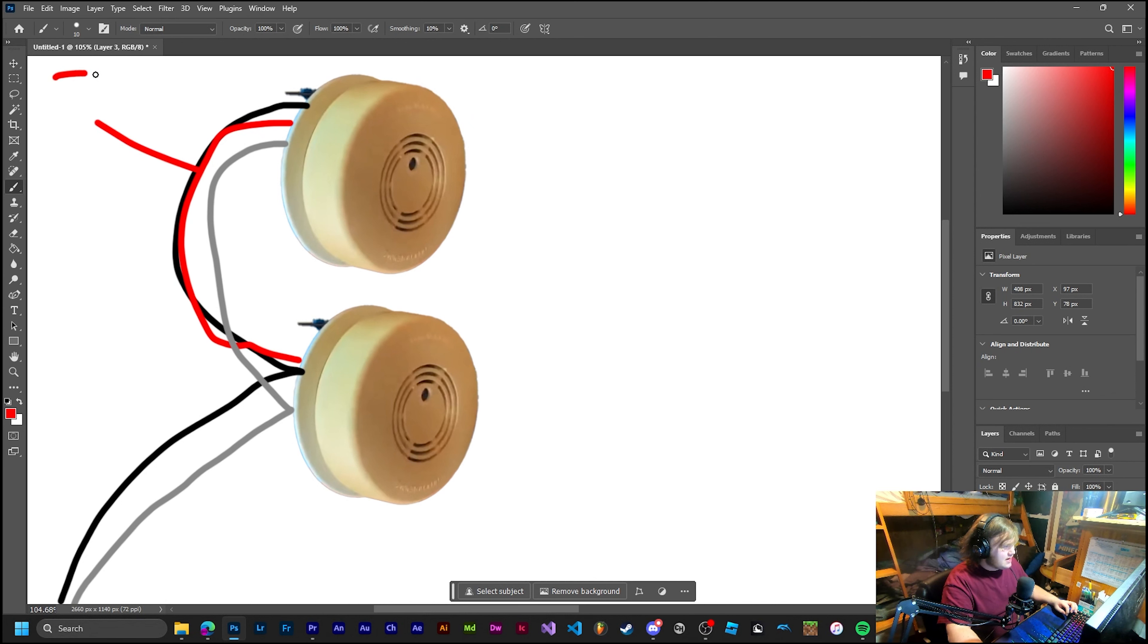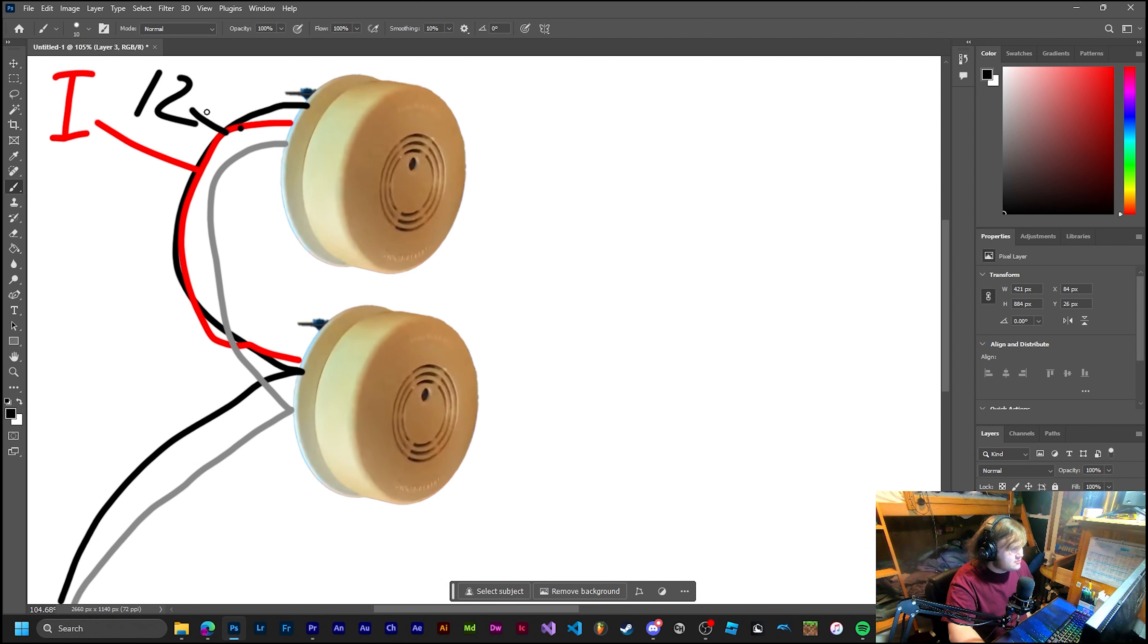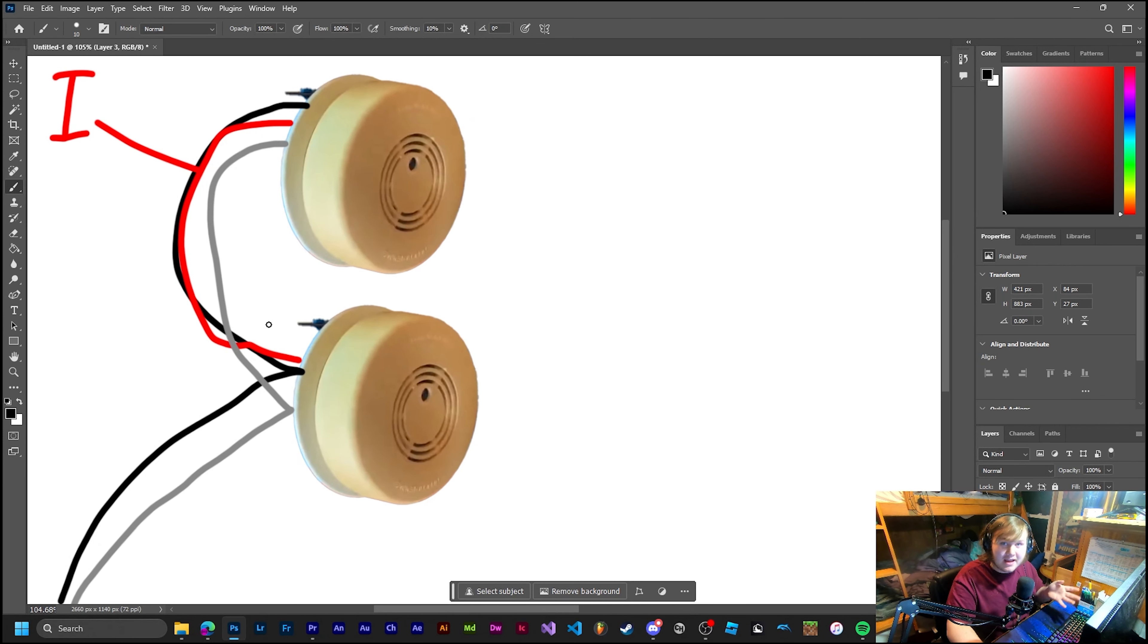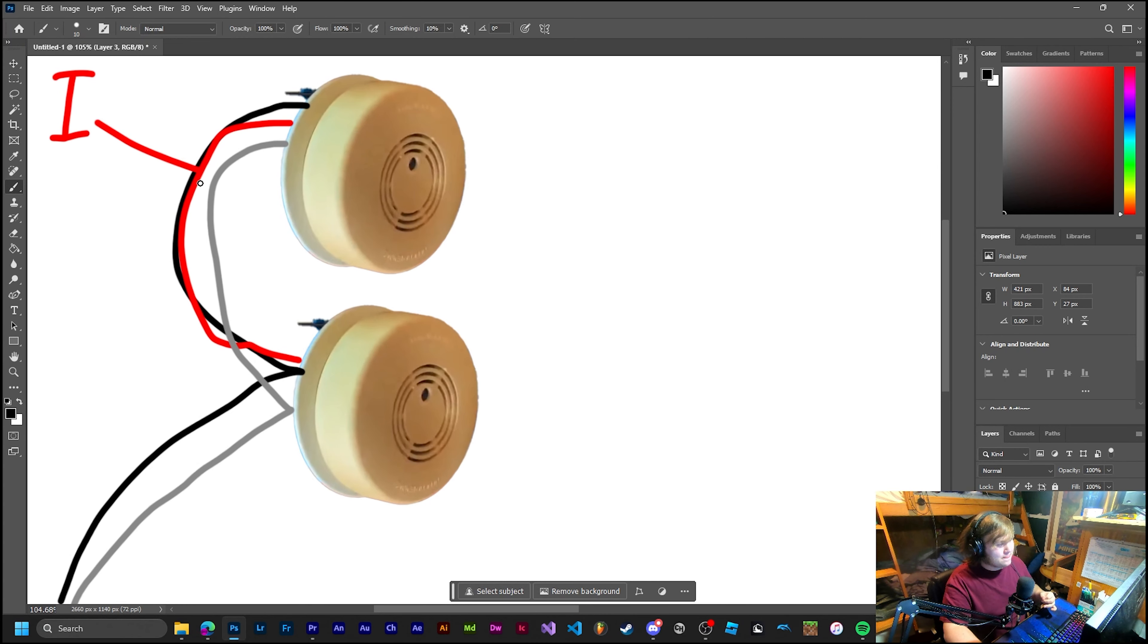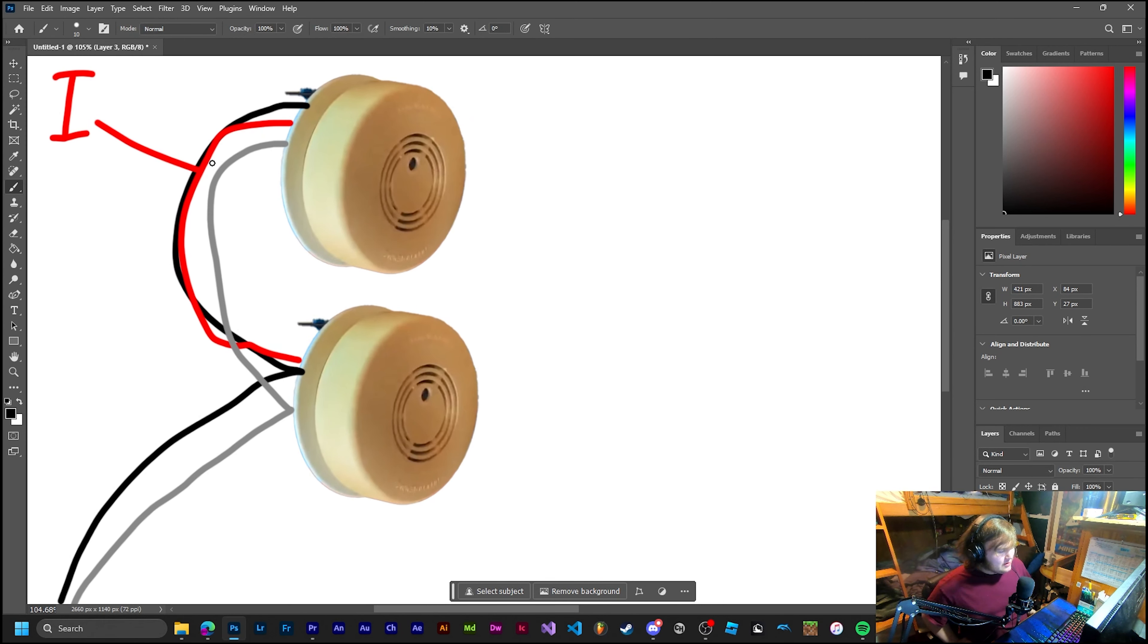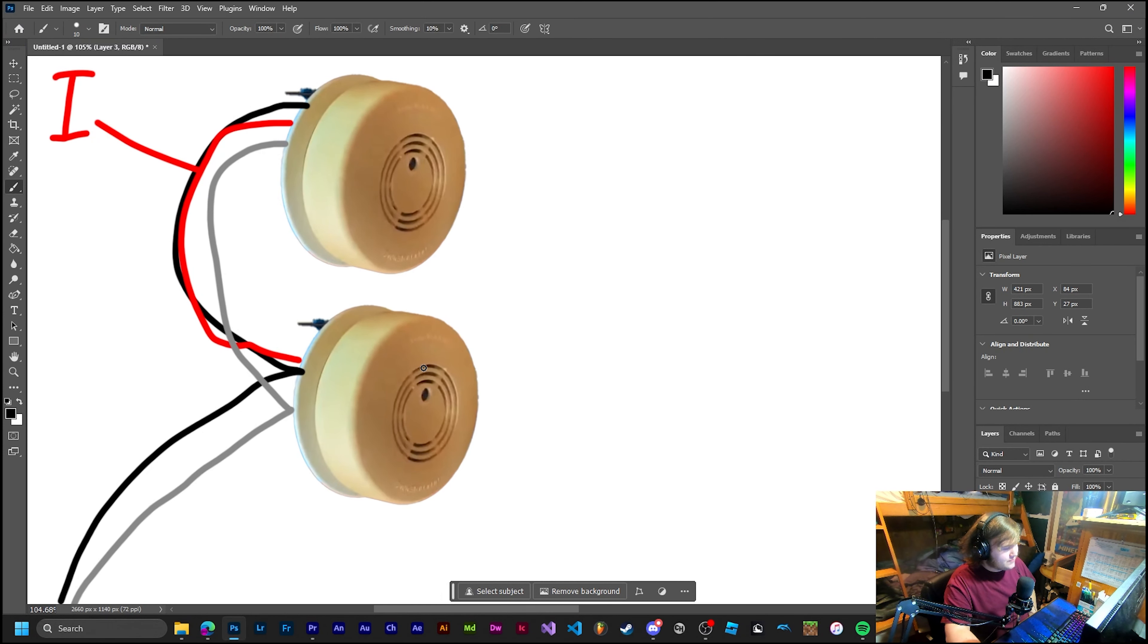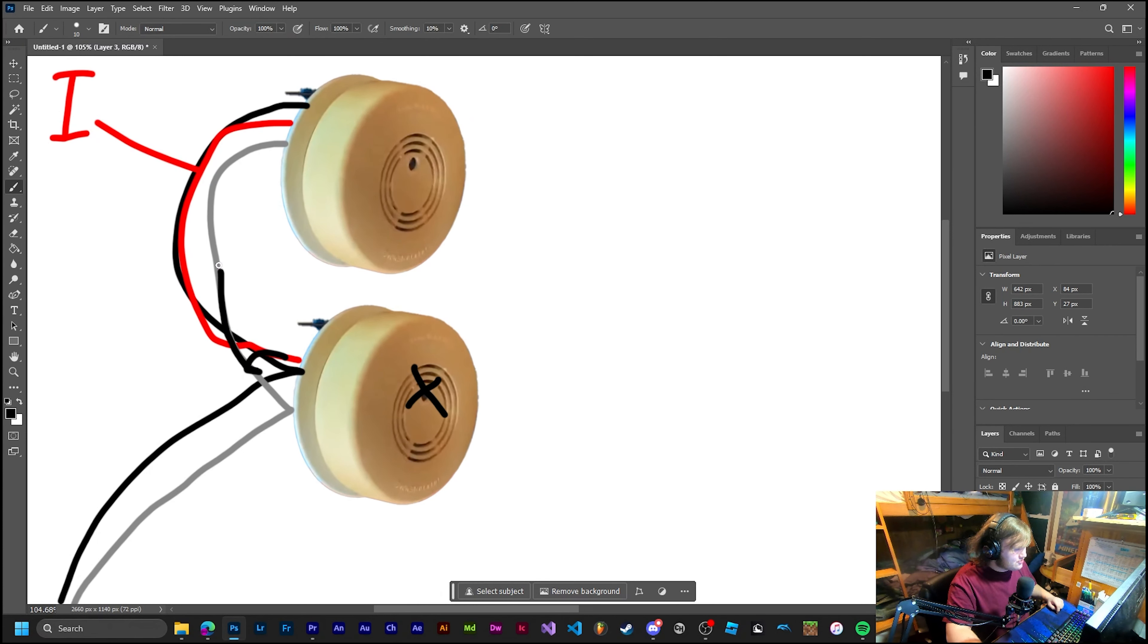This red wire is interconnect, so let's mark that with an I. What happens is that this is constantly being fed 120 volts AC. So this line, the red wire, is constantly live with AC power, and so is the black wire. But this red wire serves a very different purpose as it's designed to be shorted to the interconnect line. When the alarm is in action, if you power this one, say by pressing the test button, it will jump these two so that this is powered, and it will also make the horn in that one sound.